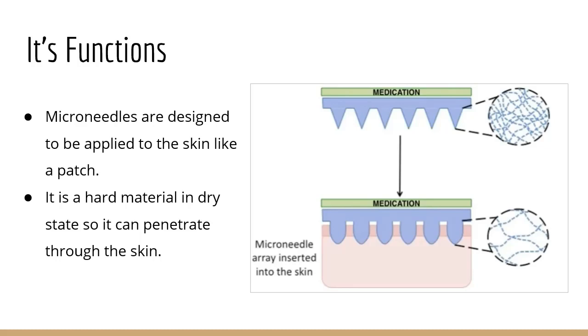This creates microscopic pores and it is through this jelly material the medication is delivered into the dermal layer of the skin that is rich in blood vessels. It can also pick up biomarkers and medicines that are already in the patient's body for monitoring purposes. The needles are so fine and small, the dermal nerves and the blood vessels are unaffected, therefore resulting in no pain or bleeding when the patch is pressed on the skin.